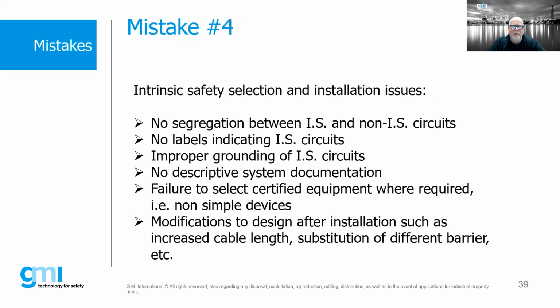So another mistake area - intrinsic safety. There are problems on IS too. Some of the biggest issues - we did a webinar on some of the big mistakes on IS particularly - you can certainly make mistakes: no segregation between intrinsically safe and non-intrinsically safe circuits, no labels indicating IS circuits, improper grounding of intrinsically safe systems.